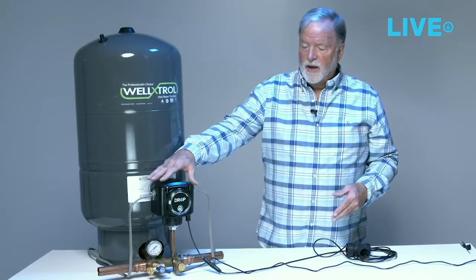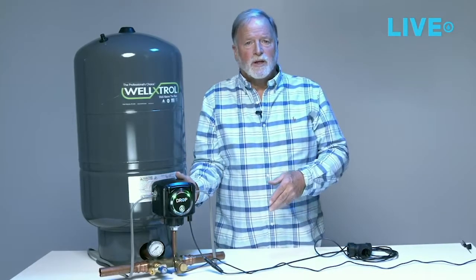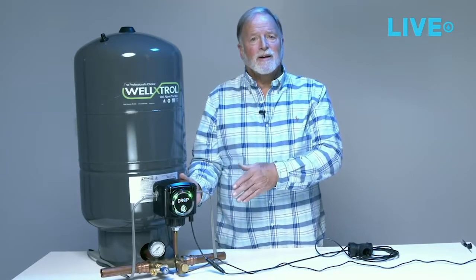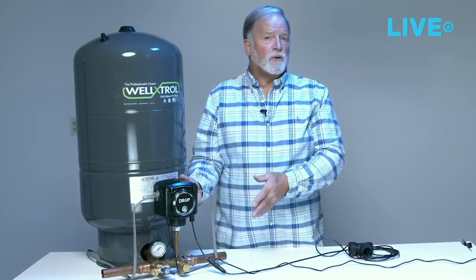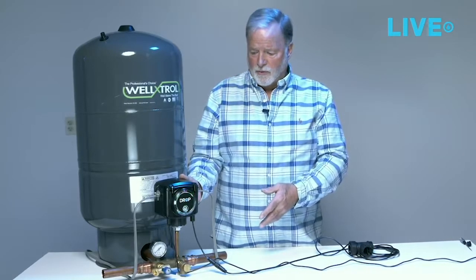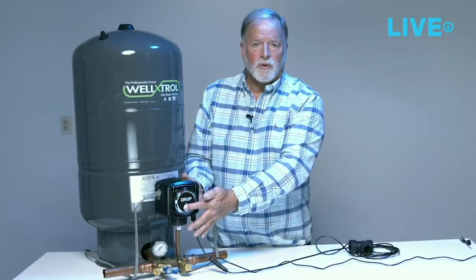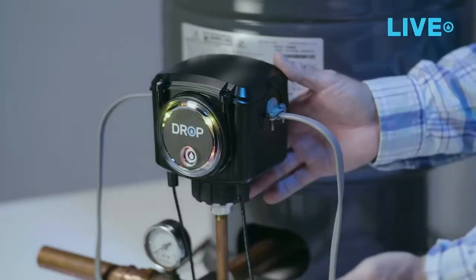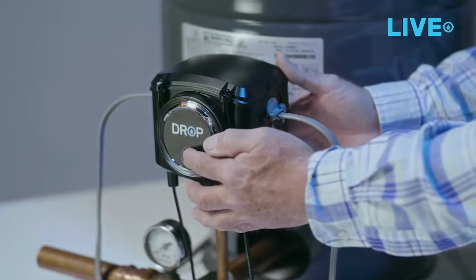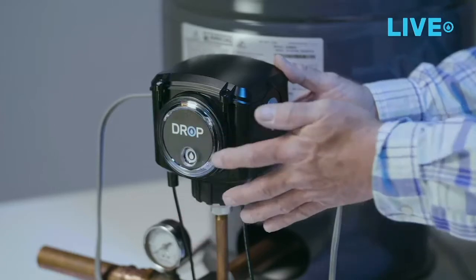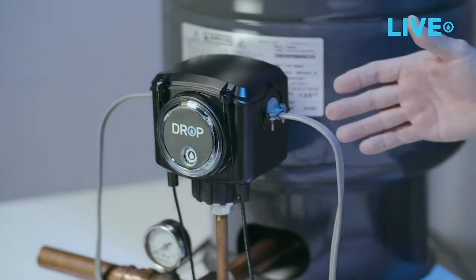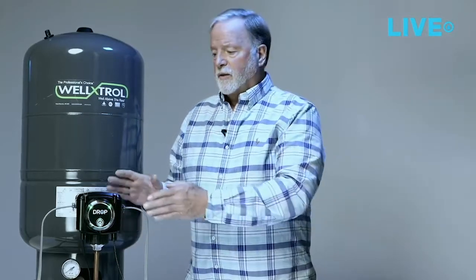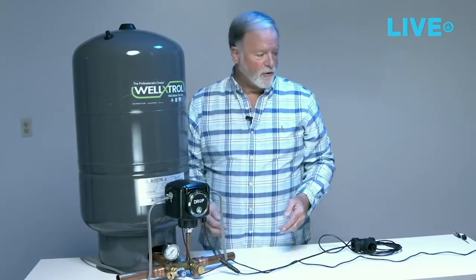We start off in this application and we've designed this switch of a high impact plastic that's UL rated for 3R, which means that we can run it indoor or outdoor. It has the touch control on the front that interfaces with the drop modules that you can actually use to turn the pump on and off right on the outside of the module. This comes in handy when you're trying to troubleshoot a system and you want to make sure that the electrical components are working, but you aren't necessarily sure how the pressure components are working. So in this case, I turned it back on.